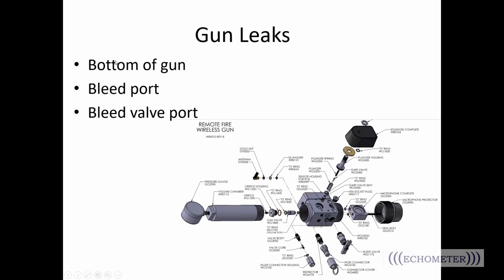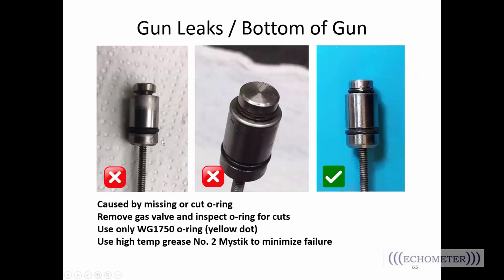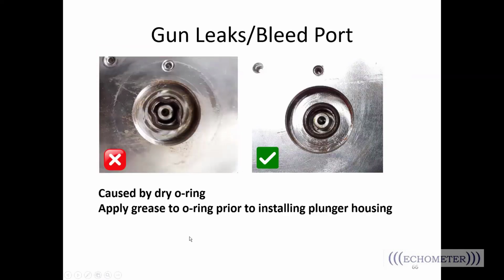What if your gun leaks? If it's leaking out the bottom of the gun, the bleed port or the bleed valve port, it could be caused by a missing or cut O-ring. Remove the gas valve and inspect those O-rings for cuts. Make sure that you're using the right O-ring replacement. Here you see the yellow dot, nice green check mark there, and use the high temperature grease to minimize failures. Here we have the bleed port. This is caused by a dry O-ring. Make sure you're applying grease to your O-rings prior to installing the plunger housing.